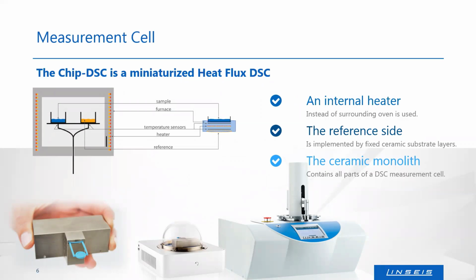The special thing about the system I want to talk about today is the measurement cell. With the chip DSC, we've changed the measurement cell a bit. Here on the left, you can see the classic layout for DSC. You have a surrounding oven with the heater, and inside this oven you can find a sample crucible and also a reference crucible with the thermocouples.